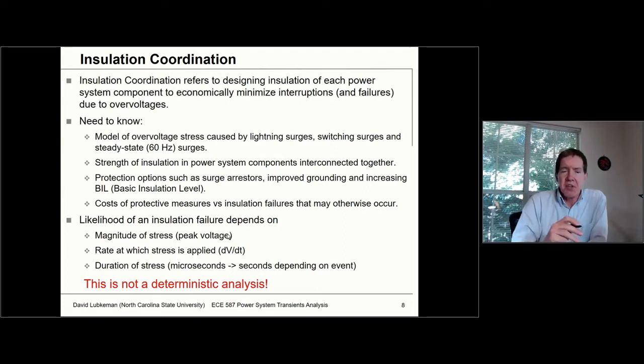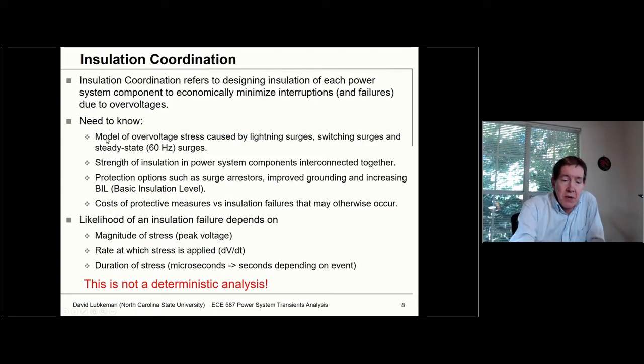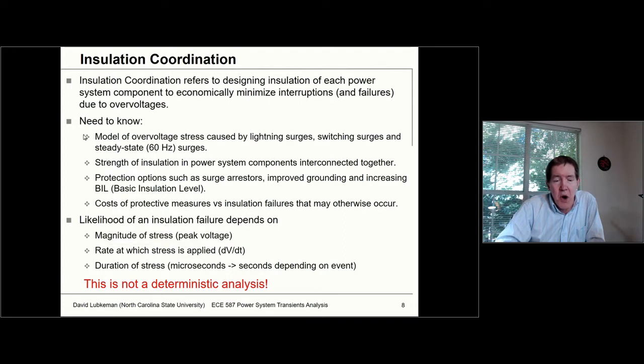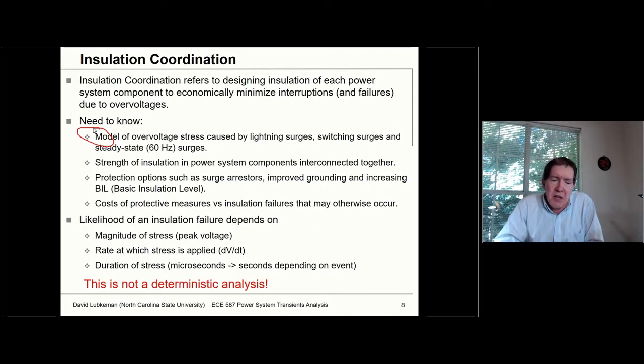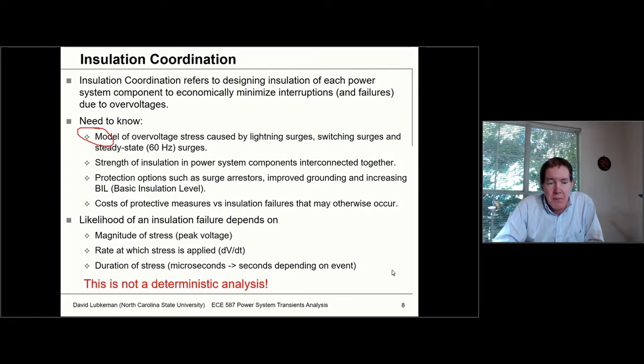What you need to know for insulation coordination is how to model the overvoltage stress — quantifying the values for overvoltage. This is where tools like PSCAD are useful. We also need to know something about the strength of our insulation, which is given in various tables in manufacturers' data sheets. What we're getting into in this specific lecture is protection options, and particularly the use of surge arrestors.